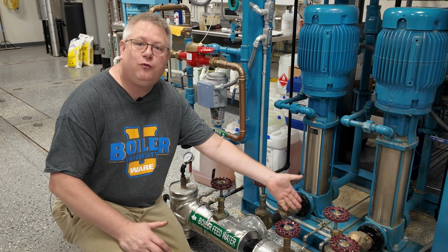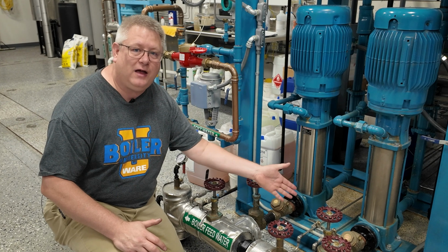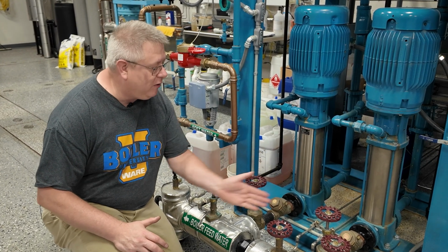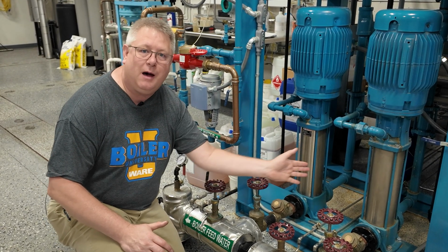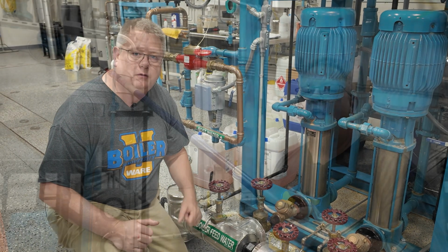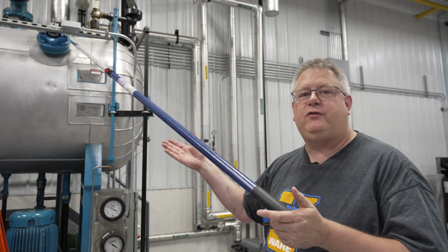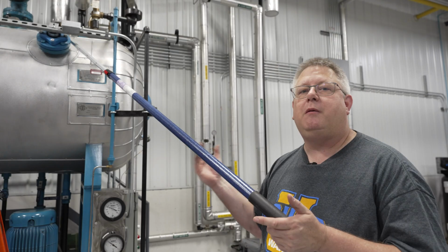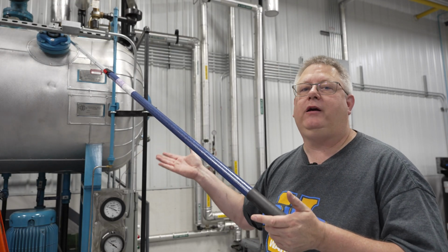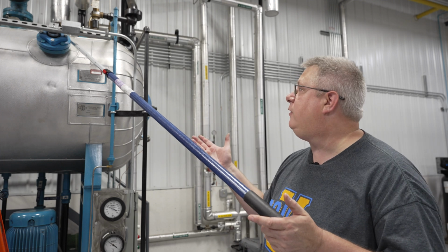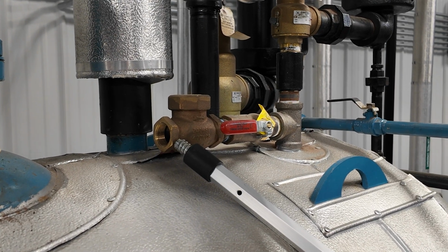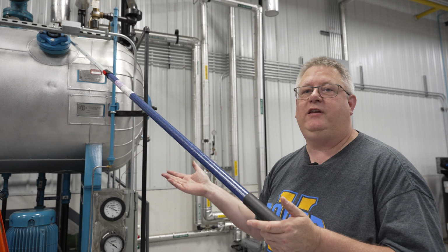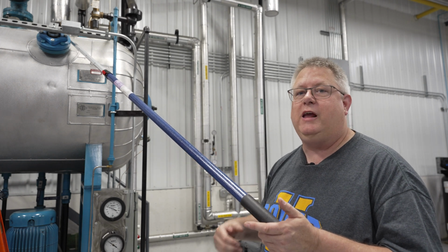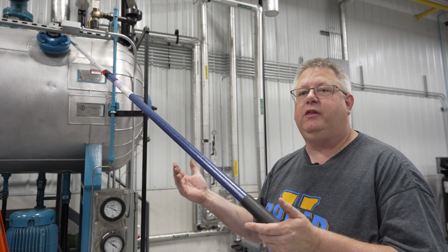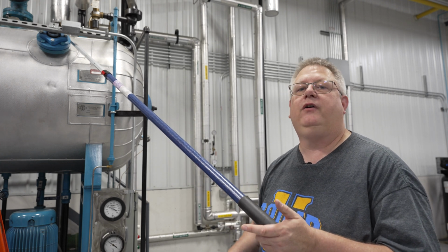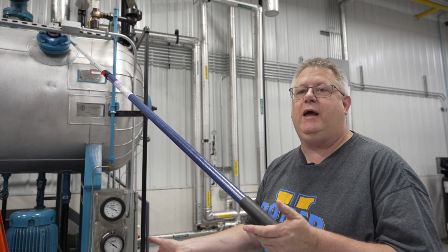Now, just a word of warning, if one of these fails, you're gonna get less capacity out of this pump because part of the water is gonna be going back through that pump. So that's a good check valve to keep an eye on. If you see a check valve on a pressure vessel or on a heat exchanger, it's probably serving the role as a vacuum breaker. So if we have a sudden drop in pressure on the deaerator, it's gonna allow it to suck in air and prevent additional cavitation of the pumps. On a heat exchanger, a vacuum breaker is typically there to allow air in to facilitate draining of the heat exchanger when there's no demand.